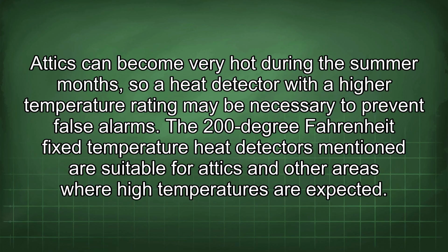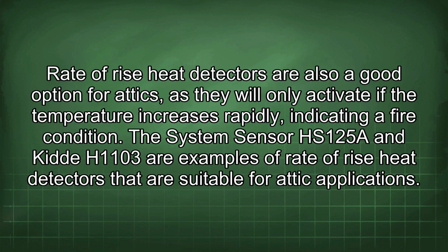The 200-degree Fahrenheit fixed temperature heat detectors mentioned are suitable for attics and other areas where high temperatures are expected. Rate of rise heat detectors are also a good option for attics, as they will only activate if the temperature increases rapidly, indicating a fire condition.